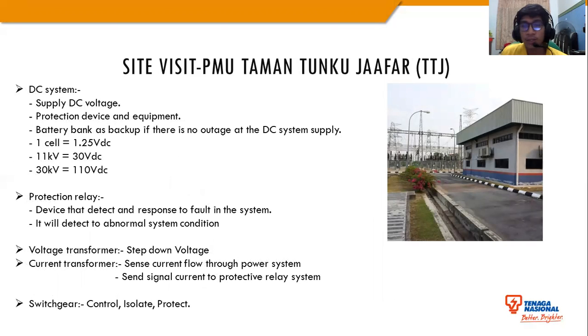Next, I would like to talk to you about the DC system in the PMU. It is used to supply the DC voltage to protection devices and equipment. The battery bank is a backup if there is an outage of the DC system. So this is one cell. One cell equals 1.25 VDC. For 11 kV, 30 VDC, and for 33 kV, 110 VDC.